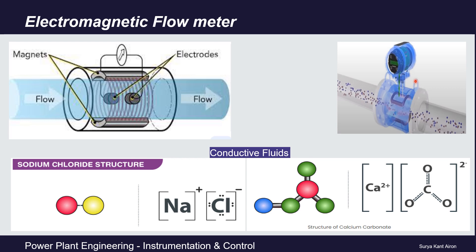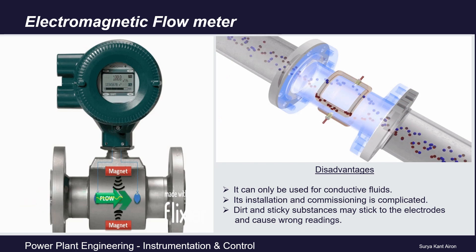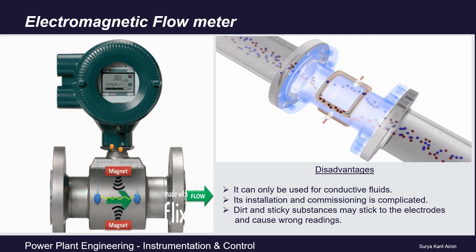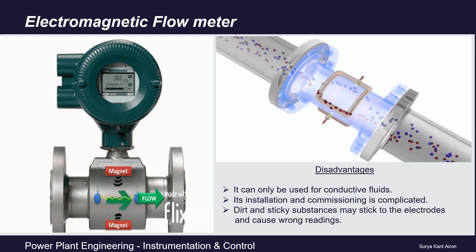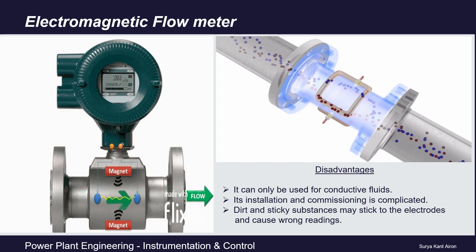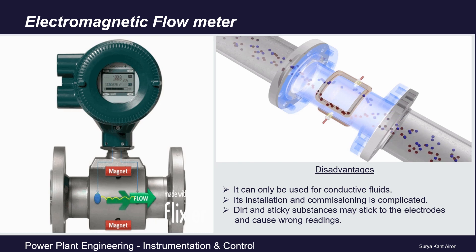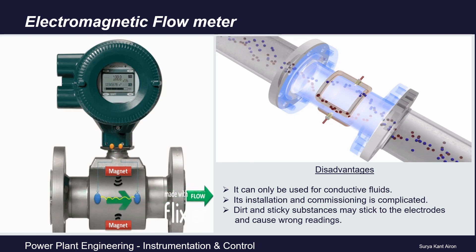The basic condition is that the fluid must be conductive — the conductivity must be greater than five micro-siemens per centimeter. The fluid should have positive and negative ions, like salt NaCl which has sodium positive ions and chlorine negative ions, or calcium carbonate with calcium positive and carbonate negative ions. If salts are removed from water to produce demineralized water, its conductivity is nearly zero, so electromagnetic flow meters cannot be used for DM water — the flow meter will always show zero reading irrespective of the actual flow.